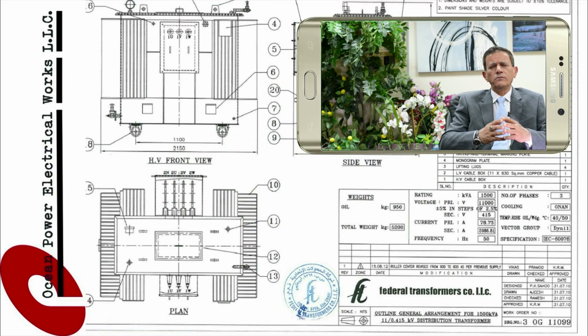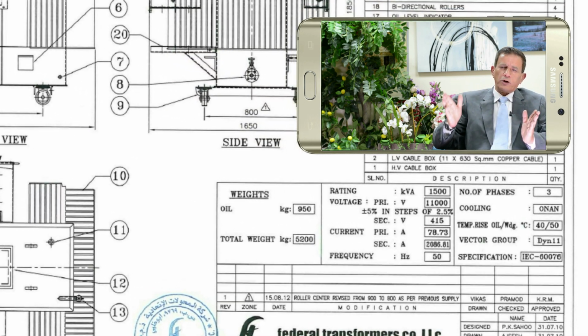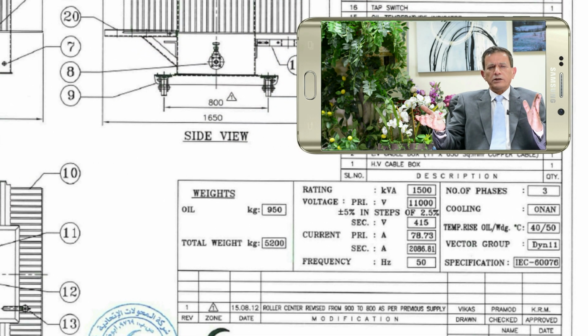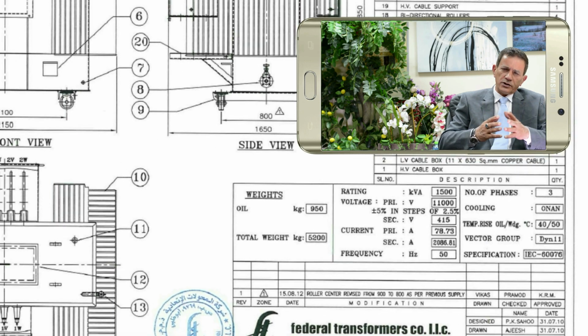So for the transformer, we are going to measure the insulation level between the low voltage and earth, high voltage and earth, and also low voltage to high voltage. And our transformer, which is under consideration, is 11 kilovolt to 400 volt. Low voltage is 400 and the high voltage is 11,000 volt.